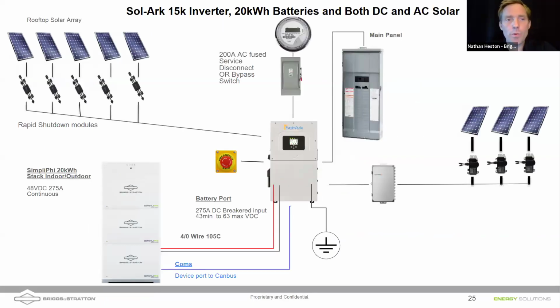Okay, here's an example where we're looking at a larger overall system, and this system is showing both AC and DC coupled solar, right? We've got a microinverter array on the roof. I can think of an example in my mind where somebody had this. They had about a 40 amp maximum array on the roof, and it wasn't quite enough to feed all the power, right? And so they wanted to add another solar array, but they also wanted batteries at their location. And so what they did is they kept that AC coupled array. They fed that in through the generator port on the Sol-Ark, but they also brought in, through the Sol-Ark has direct connections for DC solar as well.